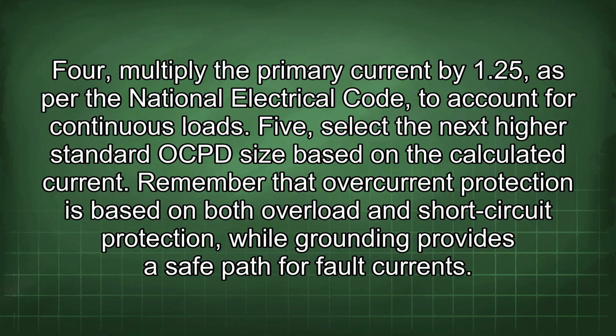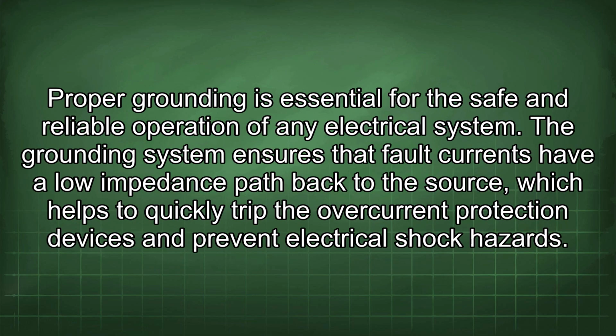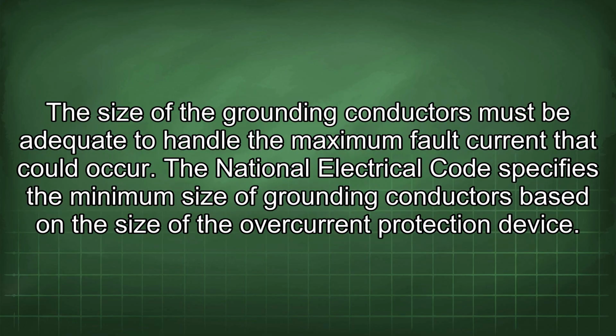Remember that overcurrent protection is based on both overload and short circuit protection, while grounding provides a safe path for fault currents. Proper grounding is essential for the safe and reliable operation of any electrical system. The grounding system ensures that fault currents have a low impedance path back to the source, which helps to quickly trip the overcurrent protection devices and prevent electrical shock hazards. The size of the grounding conductors must be adequate to handle the maximum fault current that could occur.